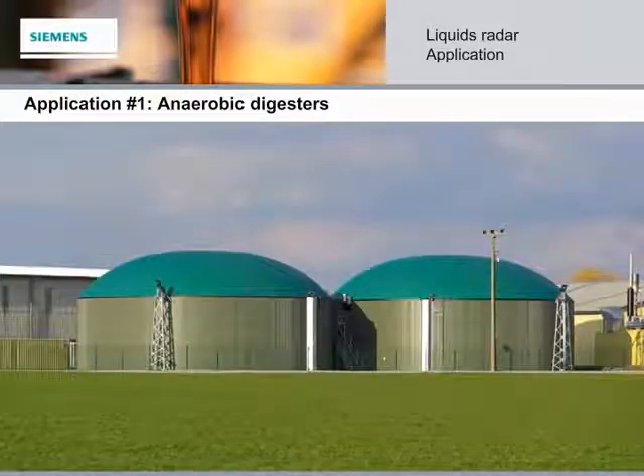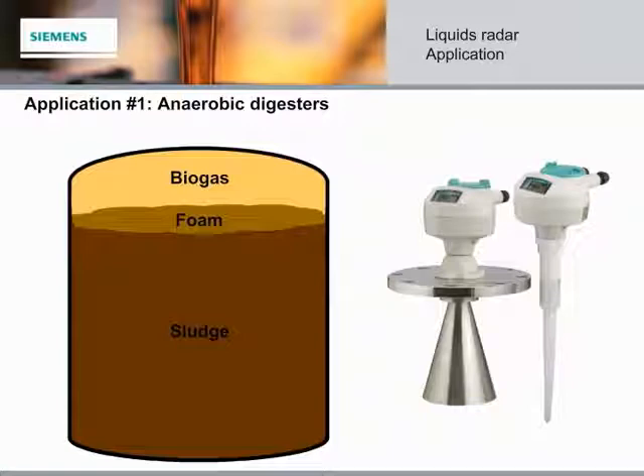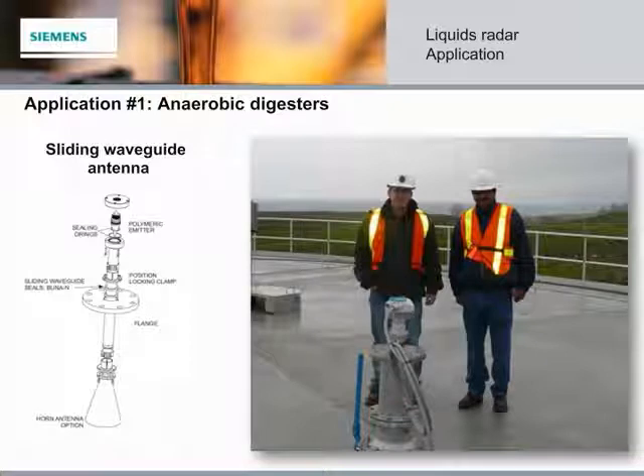Anaerobic digesters can be challenging applications due to the presence of foam on the surface, variable concentrations of vapors, and a very high concentration of CO2. The low-frequency, explosion-proof, or intrinsically safe SITRANS LR200 overcomes these challenges and measures the total level as it reflects from the foam surface. Our sliding waveguide antenna is the perfect addition, allowing you to slide the horn antenna up and out of the application while closing the valve — eliminating the need to shut down the tank and degasify, making it safer and easier to maintain.